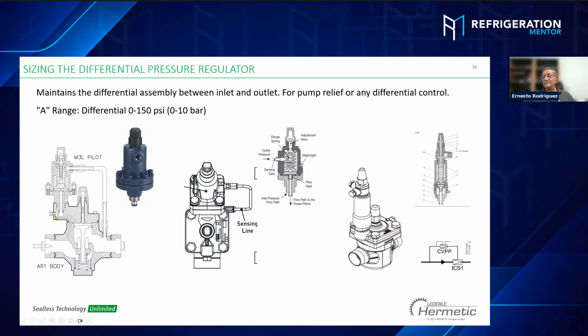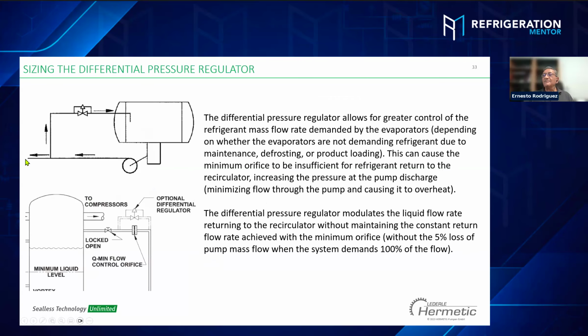We want to calibrate the pump. Our pump is running with a 45 psi differential. We want to calibrate this regulator. We have the gauge right here, and we're going to open the stem little by little until we get the 45 differential on this regulator. It means when you exceed the pressure discharge on the pump, instead of the pump stopping on high differential pressure, this liquid is going to return back to the vessel.